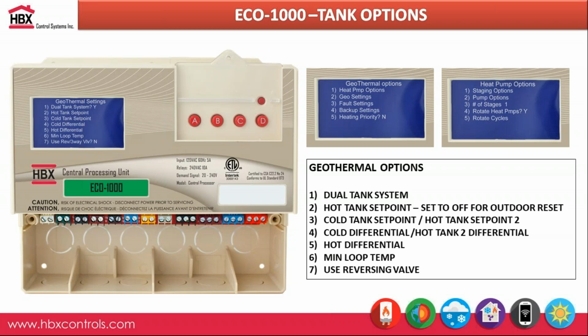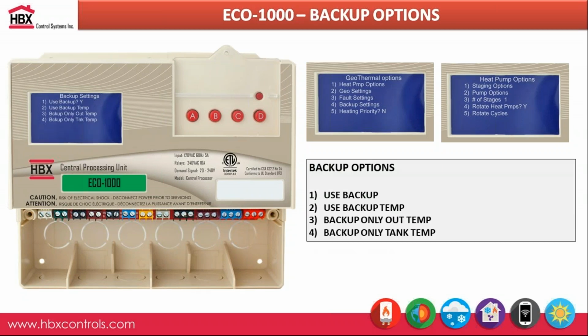So if you're just transferring heat, you want one tank to always be hotter than the other, just for storage purposes, you have that option with the 1000 to control up to two tanks, and both would go off of outdoor reset if you wanted to on there. You can have a hot and cold tank differential for both your tanks on there. So that really helps out for short cycling purposes as well. And you can also tell the controller that we're using that last relay on the 1000 to operate the reversing valve to switch over from heating to cooling on there. And you can also control the ground loop temperature on the 1000 as well. So a lot of different options in terms of how you want the 1000 to control your tank options on there.